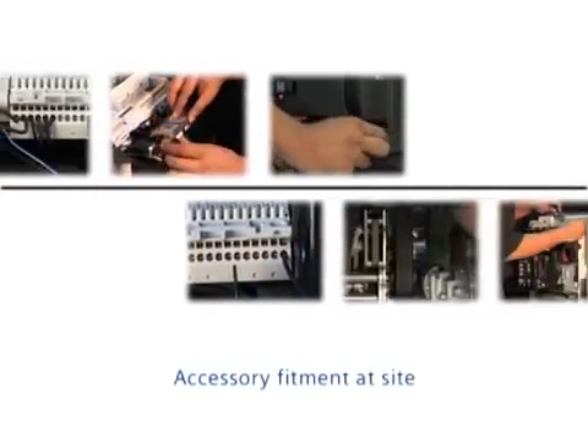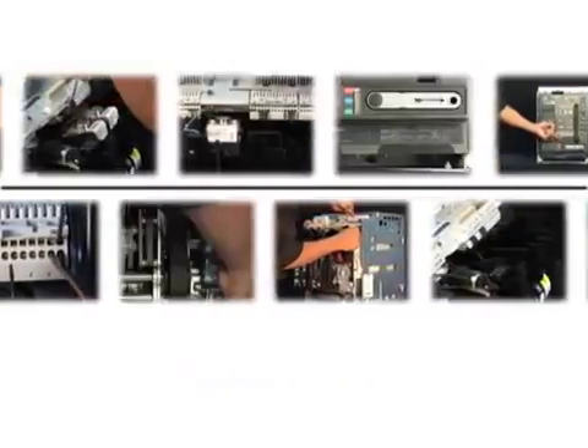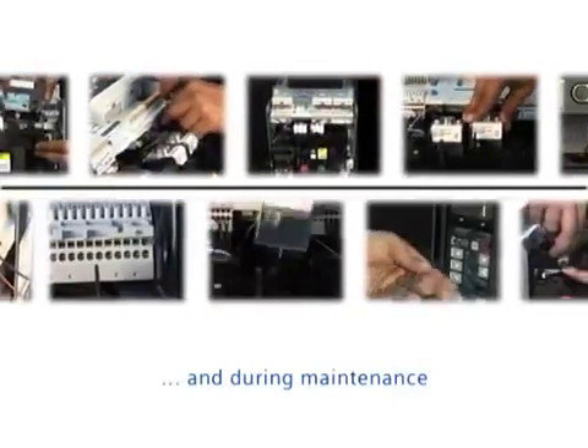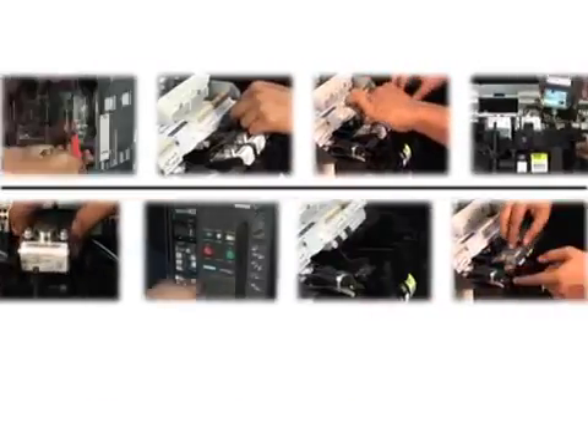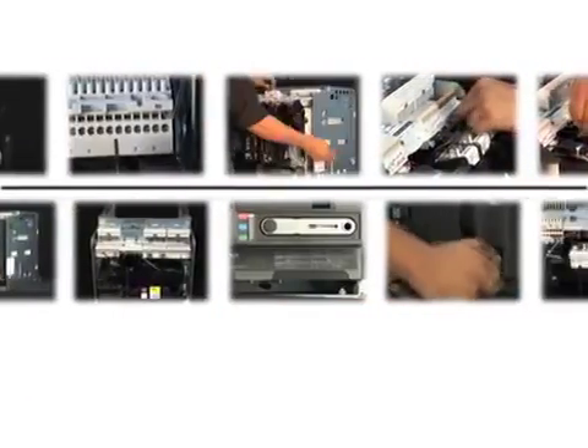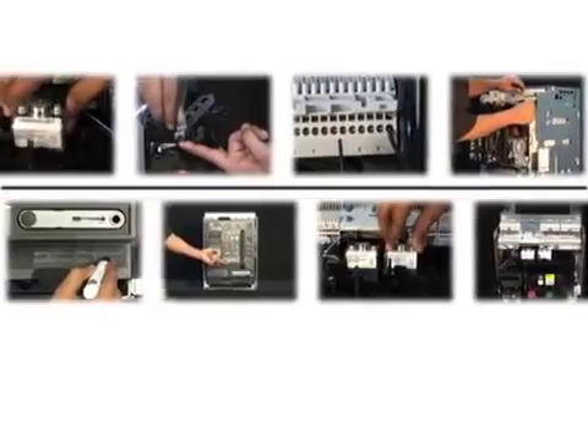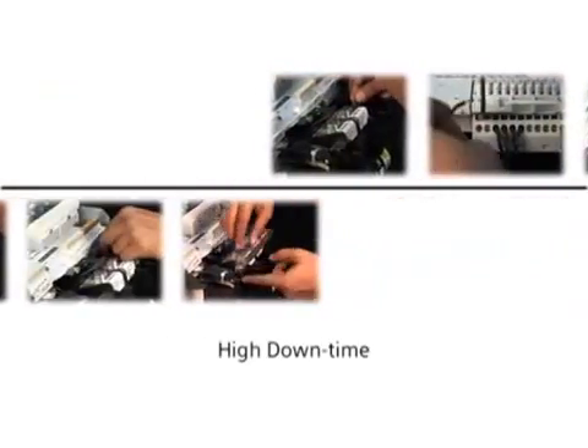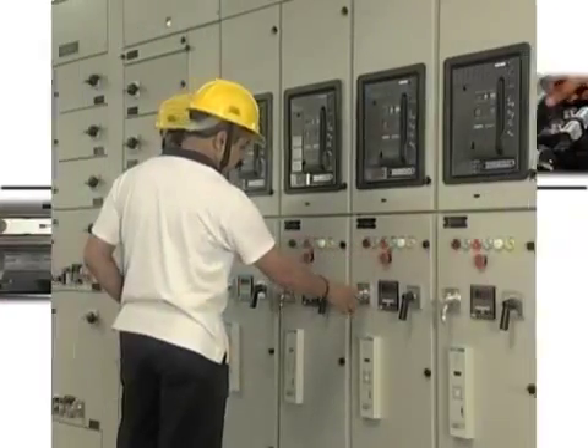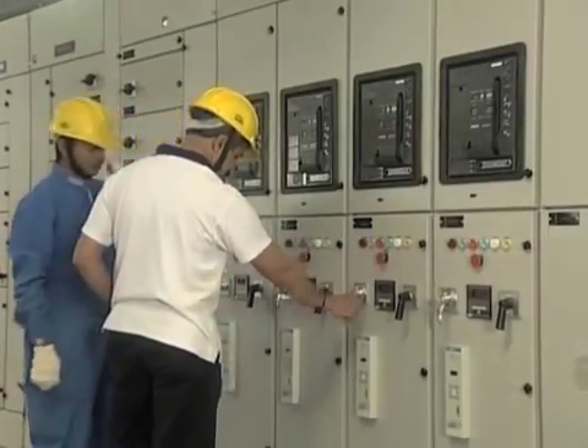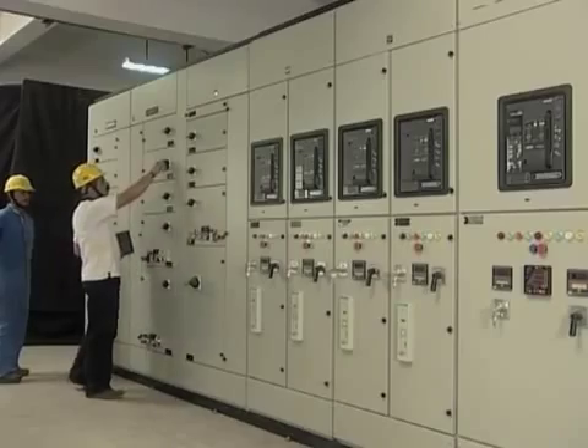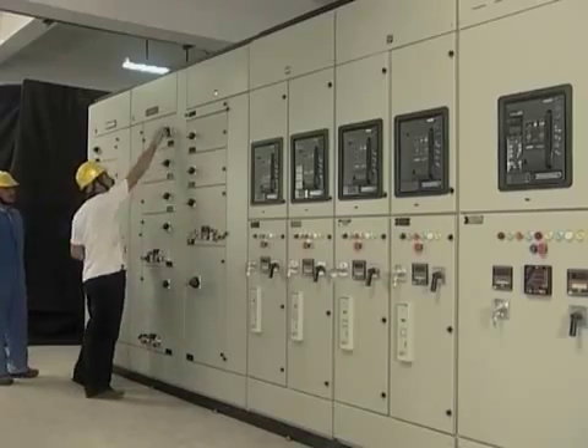So, this may lead to fitment of accessory in the breaker at site, and accessory fitment during periodic maintenance is also a need. Smooth fitment of accessories in circuit breakers is a very important factor because of high downtime. Fitment of accessory in a circuit breaker demands shutting down the particular feeder. If accessory fitment is a complex and time-consuming process, it affects the production time considerably.